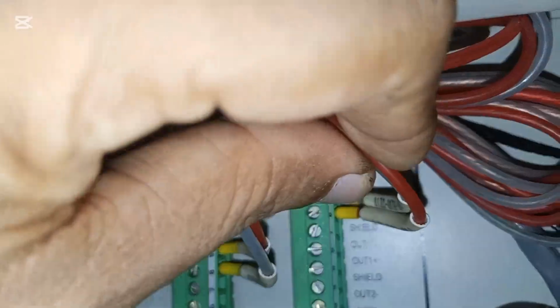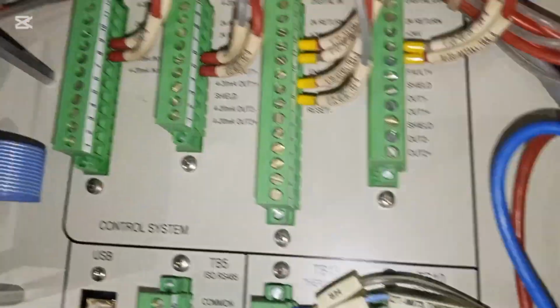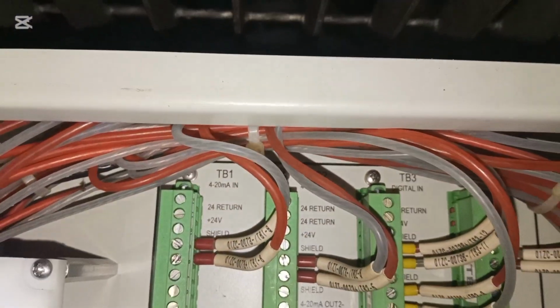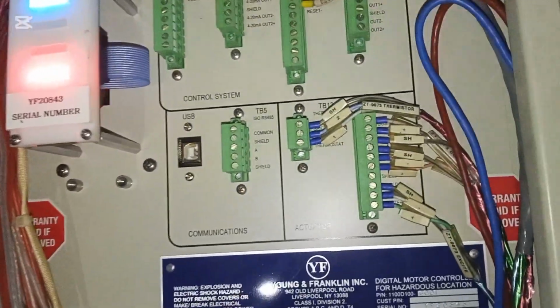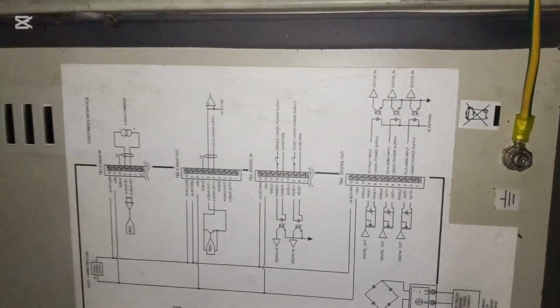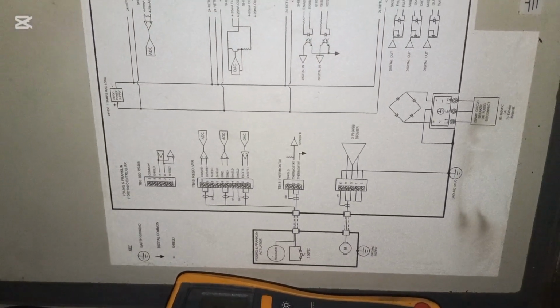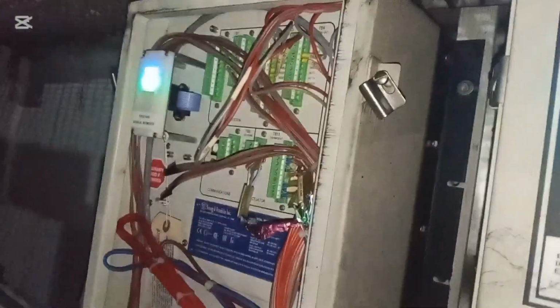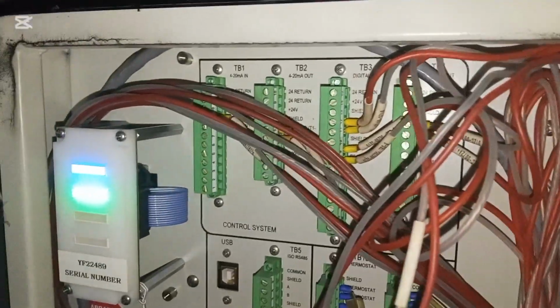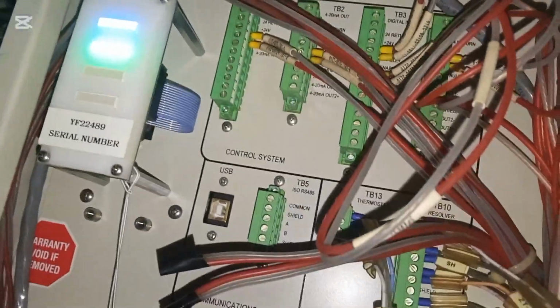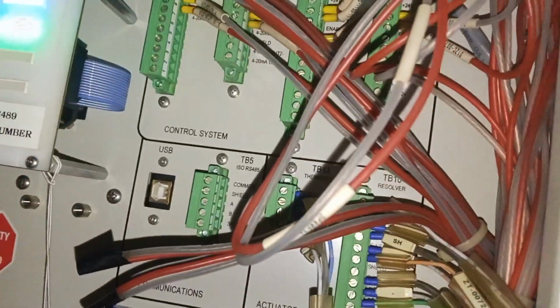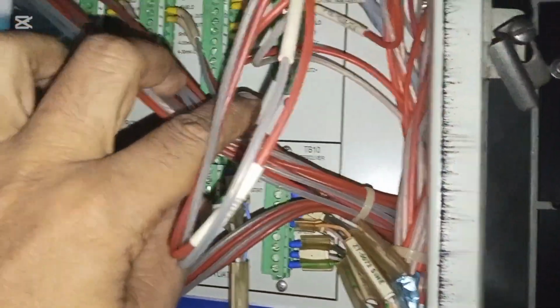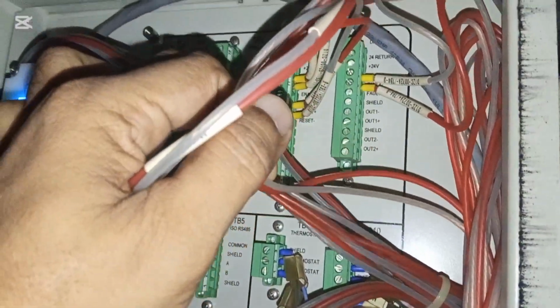Before this we checked the power supply which came to this controller from the electrical substation. We powered off the circuit breaker, and after switching on the circuit breaker we measured the power supply by multimeter, and it showed 110 volt DC, and everything was okay. We also checked the supply voltage in the field to the controller unit, which is okay. So finally we decided to change the controller unit with a new one.